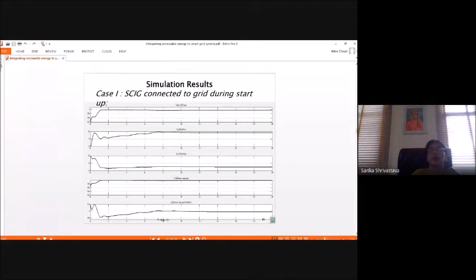When we connect the squirrel cage induction generator to the grid, there are significant fluctuations at the time of start in voltage, power, and reactive power. All such parameters are highly fluctuating, and then it becomes stabilized. If these fluctuations are very high, they may affect the system largely. The whole power system will be affected significantly, so handling this condition smoothly is a big task.